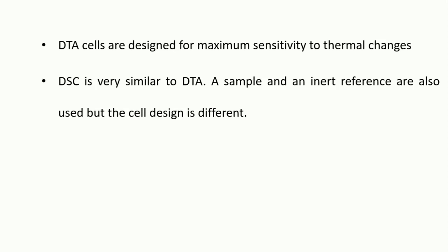Enthalpy changes are therefore measured directly. In other DSC cells, the difference in temperature between sample and reference is measured, as in differential thermal analysis. But by careful attention to cell design, the response is calorimetric.